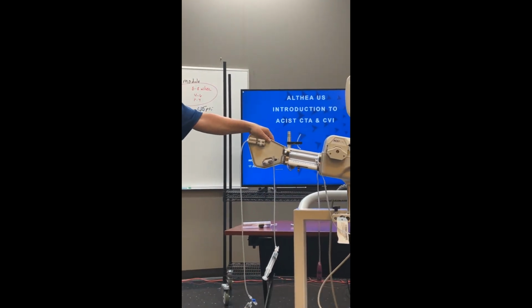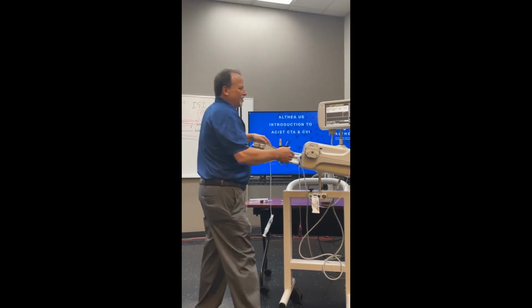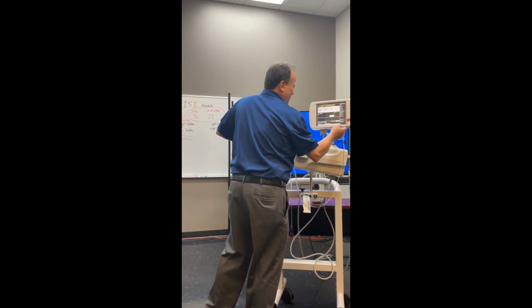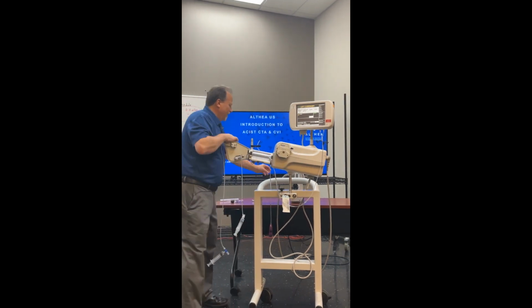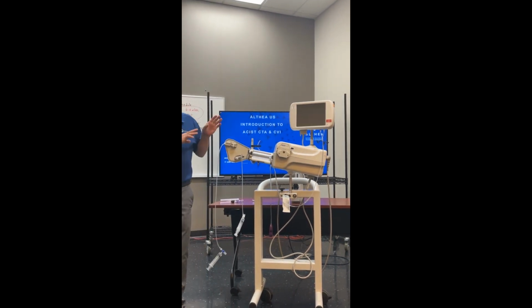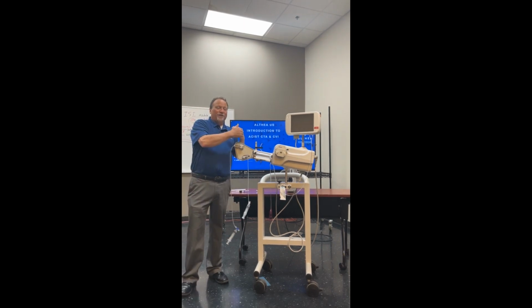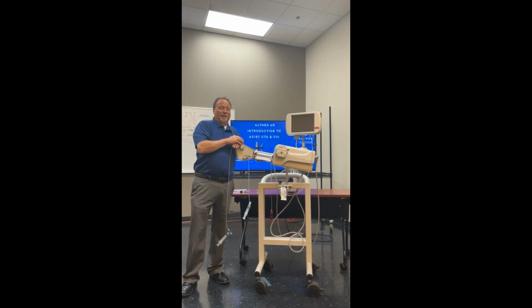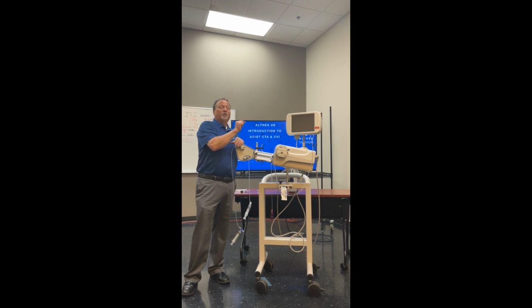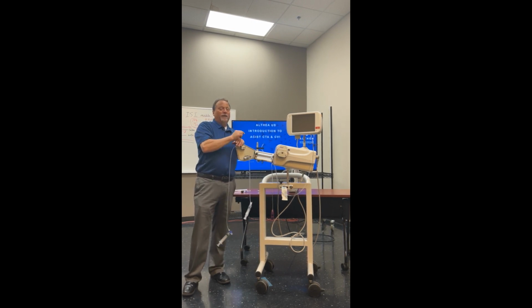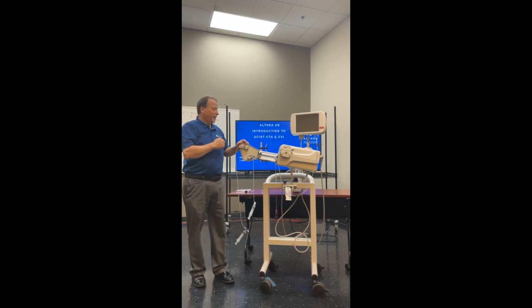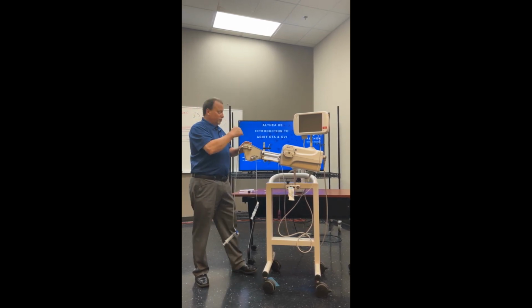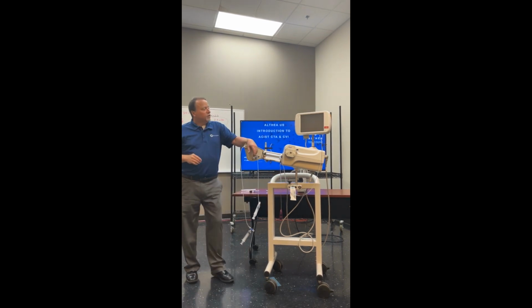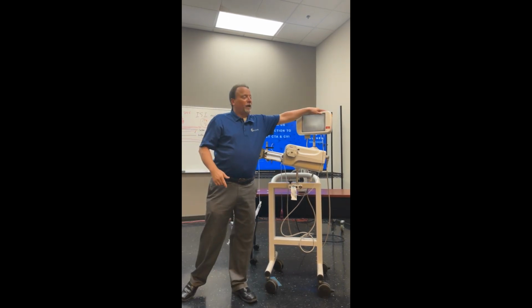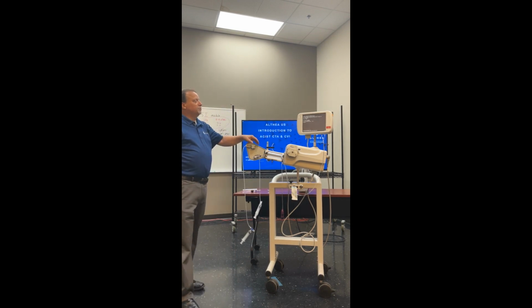So another tech support call we've had is this standby button. So I'm going to put it in standby and turn it off. Okay? One thing about this injector, if you clear an error, it doesn't automatically advance to the next segment. It will stop and you have to hit OK. If you don't hit OK, it never advances. It just stays where it's at, even though you've corrected the problem. So I'm going to turn it back on. Now it's in standby mode. I have the button pushed. So it's going to boot up.